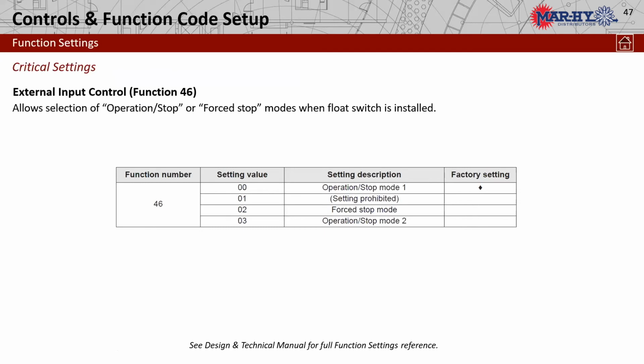Okay, let's talk about some function settings. The external input control. This is our operational force stop mode. There again, we talked about the number 1 and 2 on the low voltage terminal to be our safety switch. Here are the options. Function number 46, our settings are 00 through 03. Right now, I've gone through most of these function codes to find the one that best fits our application, and at this time, it's 03 for that function code 46.